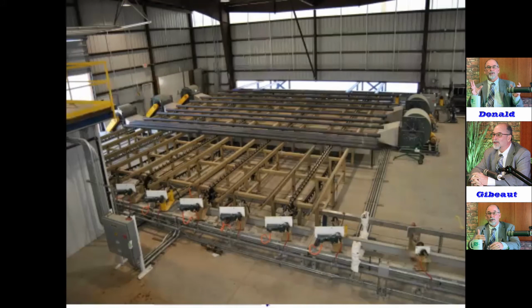Here's what those forced air convection fan systems look like. They are VFD controlled. So again, you can really control the output temperature coming off of this thing. And what that allows you to do is eliminate another induction heater at the end where you have to preheat going into a coater. And if you look up in this upper right corner, this is the coating machine. It's open right now. It closes down, the pipe goes through. But we can control how much cooling we have here to maintain below 170 degrees, but enough temperature in it to cure out that water-based coating material.